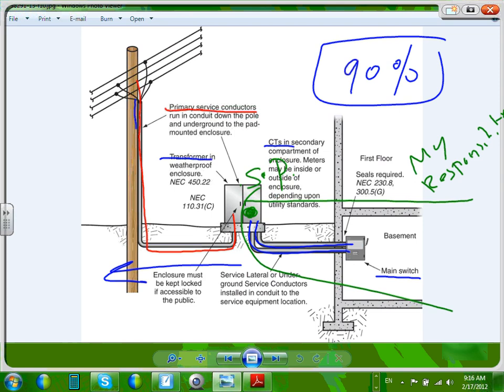You bring a feeder from overhead, from underground to a transformer, like you see. Now this conduit and that cable most likely will be installed by the utility. They might ask you to put the conduit for them, but they will pull their cables up to their transformer that they will install. Then you put your CT cabinet next to them, and you go to your building. Any questions about this?